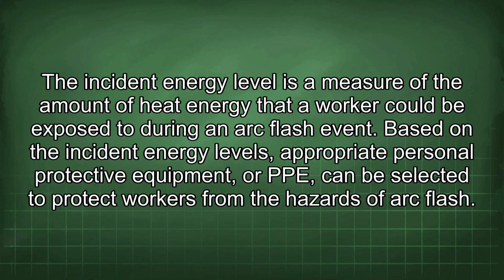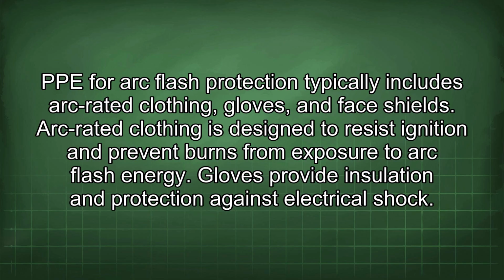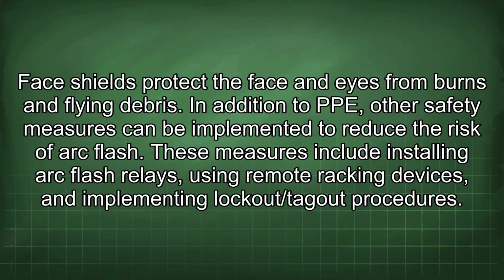Based on the incident energy levels, appropriate personal protective equipment, or PPE, can be selected to protect workers from the hazards of arc flash. PPE for arc flash protection typically includes arc-rated clothing, gloves, and face shields. Arc-rated clothing is designed to resist ignition and prevent burns from exposure to arc flash energy. Gloves provide insulation and protection against electrical shock. Face shields protect the face and eyes from burns and flying debris.